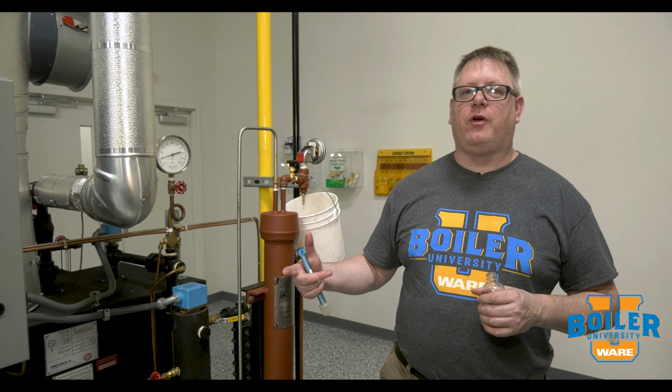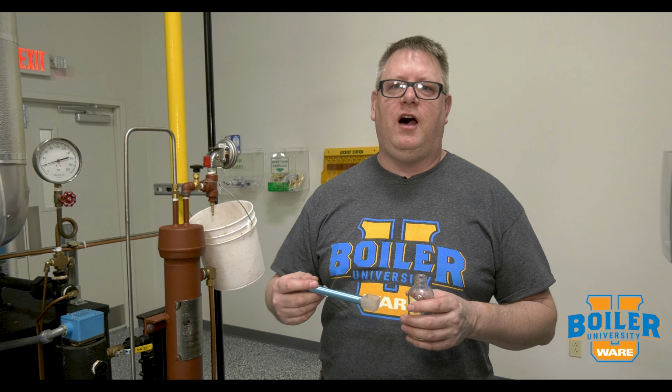This week's boiler tip, we're going to talk about conductivity and your sight glass. Looking at your sight glass daily is important because we want to, number one, make sure there's a safe level of water in the boiler, but we also want to look at how that water behaves. And one of the things that can affect the behavior of water in our sight glass is conductivity.